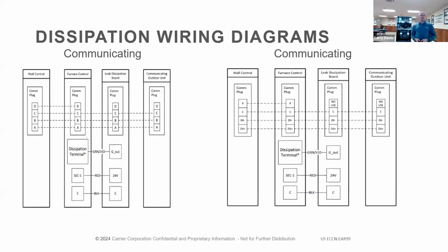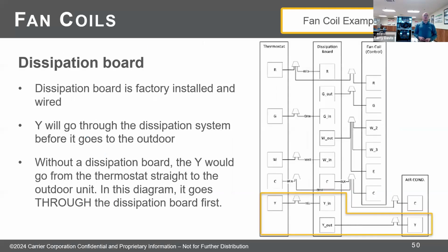There will be a dissipation terminal on the furnace board that you'll wire the G out from the dissipation board to. And what that does is that provides that output to tell the blower to come on when you're in dissipation mode. And again, you'll see the secondary 1 and common, we're wiring straight from those taps to the dissipation board. And we've got to have better slides of this going forward.